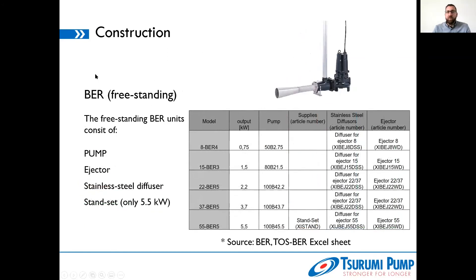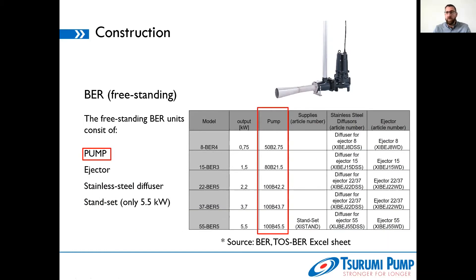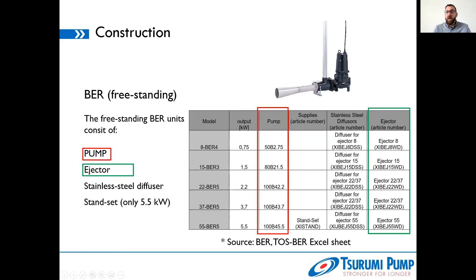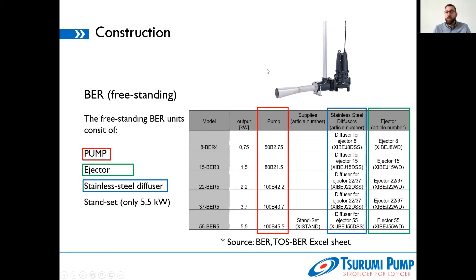For the freestanding BER, we have some minor differences. The pump is always the same — 750 watts to 5.5 kilowatts, same size and type. The ejector changes because we're not using the TOS ejector anymore — there are no guide rail fixings and no duck feet. Instead, it is a system directly mounted to the pump and ejector with minor feet to install it freestanding on the ground. The diffuser is completely identical to the TOS version. The major difference between the TOS BER and the freestanding BER comes down to the ejector type.